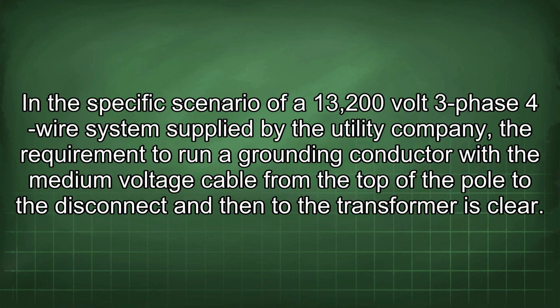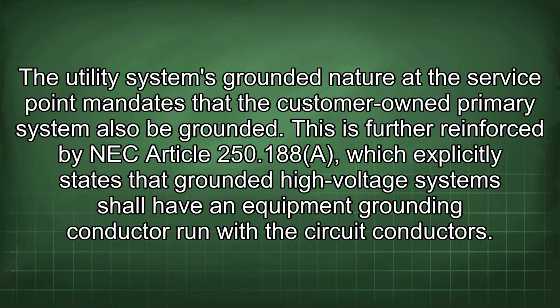In the specific scenario of a 13,200 volt 3-phase 4-wire system supplied by the utility company, the requirement to run a grounding conductor with the medium voltage cable from the top of the pole to the disconnect and then to the transformer is clear. The utility system's grounded nature at the service point mandates that the customer-owned primary system also be grounded. This is further reinforced by NEC Article 250.188(A), which explicitly states that grounded high-voltage systems shall have an equipment grounding conductor run with the circuit conductors.